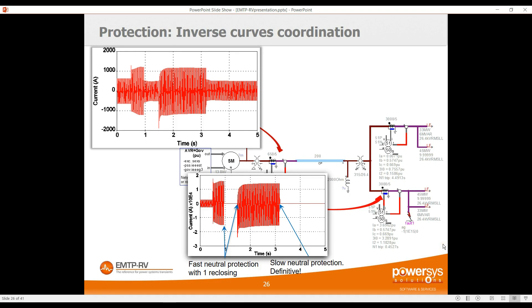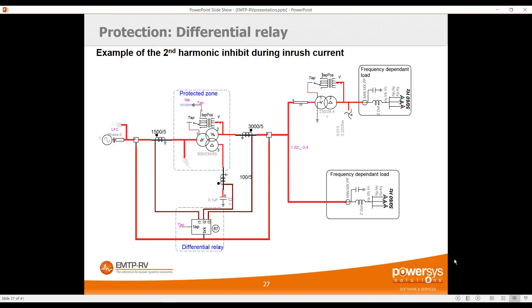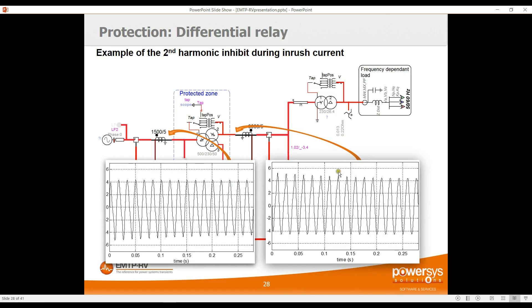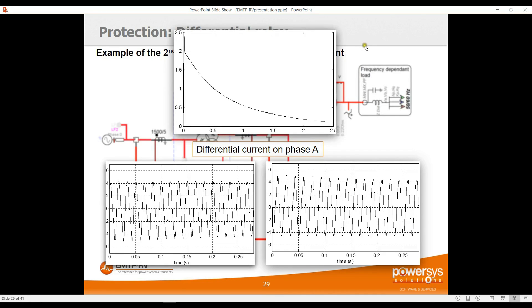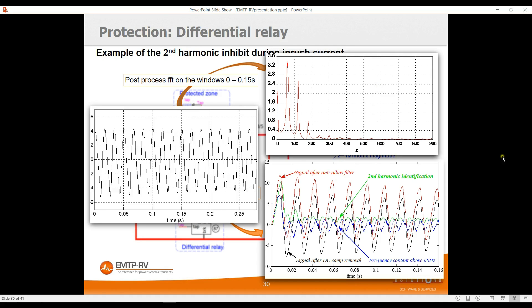Here's a typical example of a differential relay study — the energization of a transformer. As the transformer is energized, inrush current is created, generating a differential current that can cause a relay trip. We can see the current at the secondary of the CT, clearly showing the second harmonic, and the differential current reaches 2 amps at secondary — more than enough to cause a trip. The goal is to set the level of second or fifth harmonic blocking threshold. Inside the relay, the level of second harmonic is visible during simulation, and scope view can also perform a post-processing FFT showing the first, second, and higher harmonics.